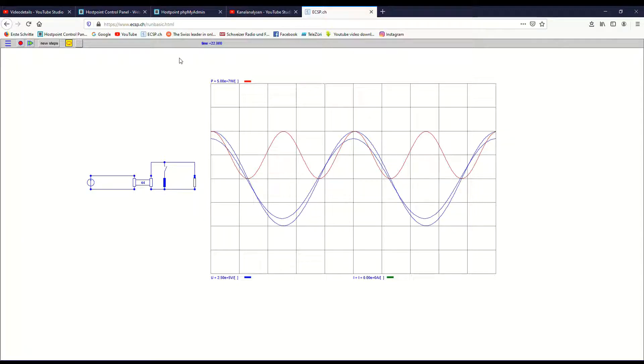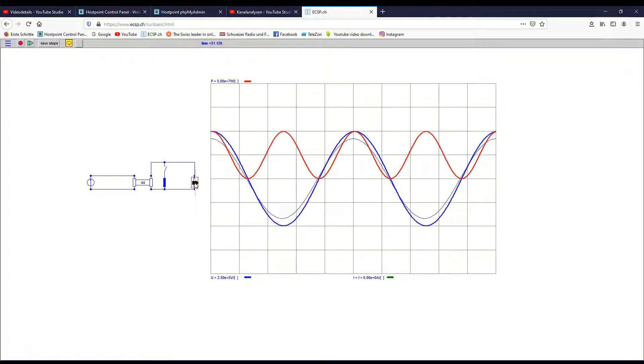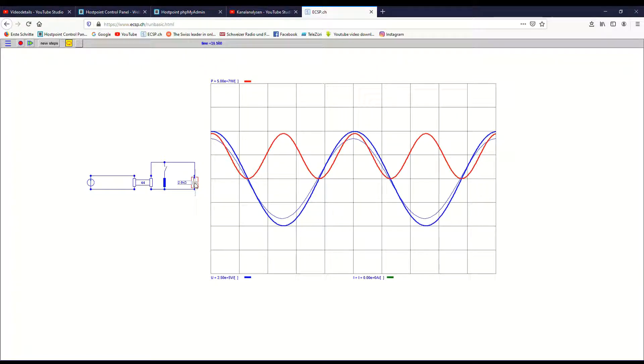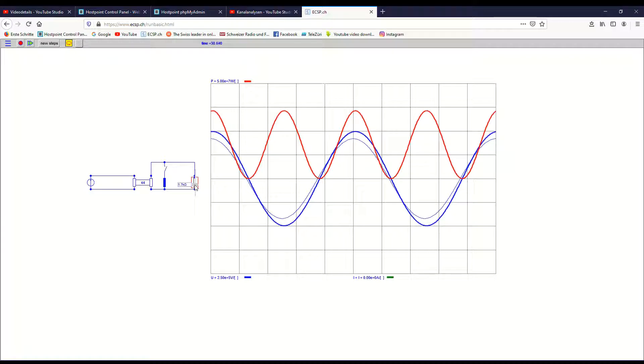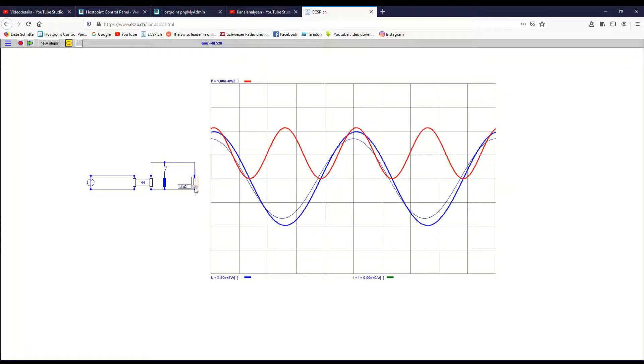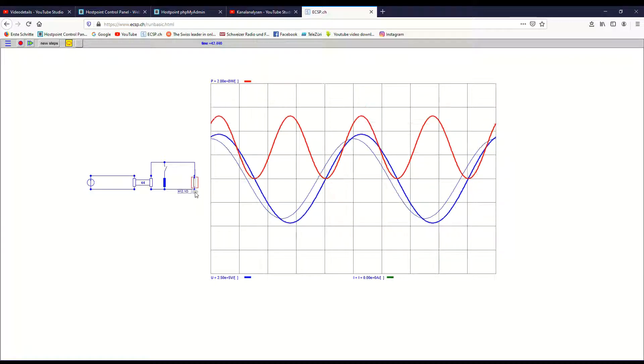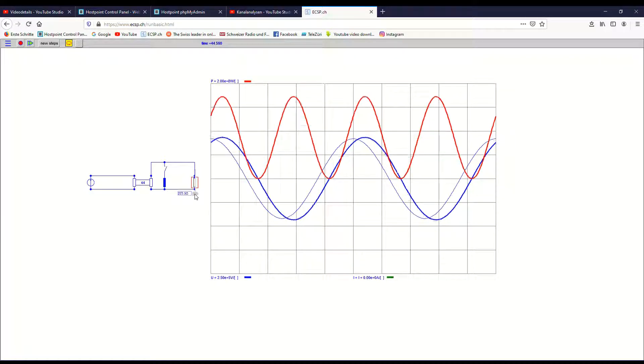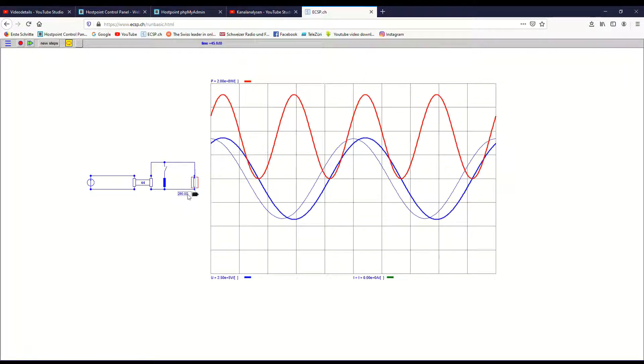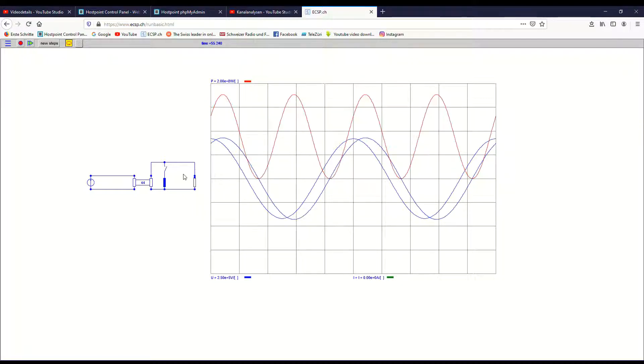To make the case I again switched off my reactor so the voltage is again higher than at the source. Now I reduce the load resistance meaning I increase the power at the load. You can see now that the voltage at the load with increasing power is diminishing. So now we have basically a load voltage which is in the scope of the nominal.